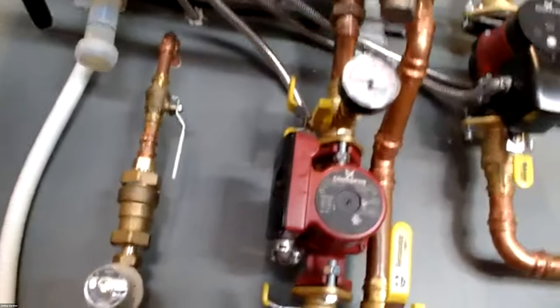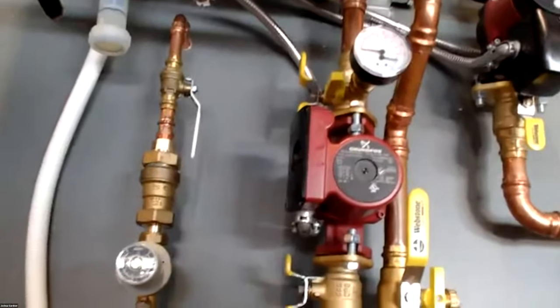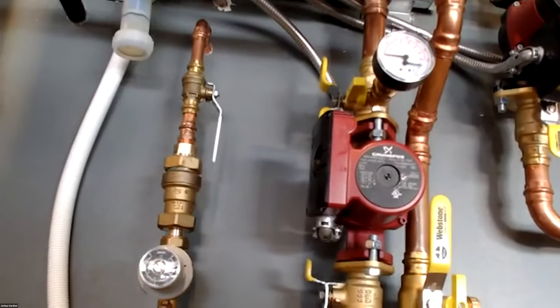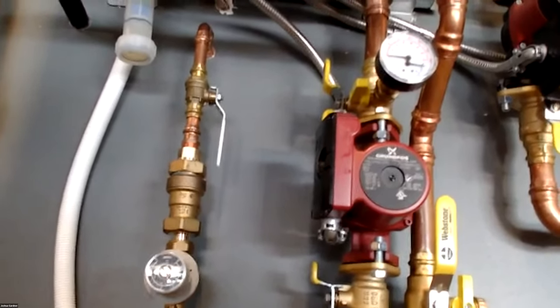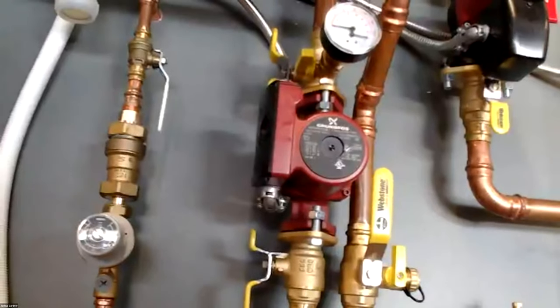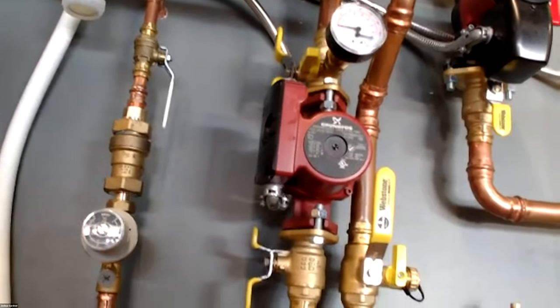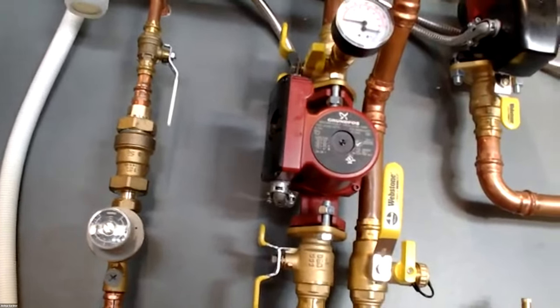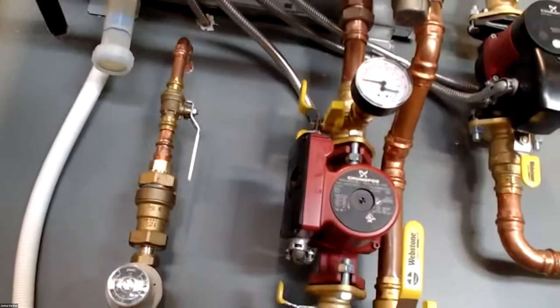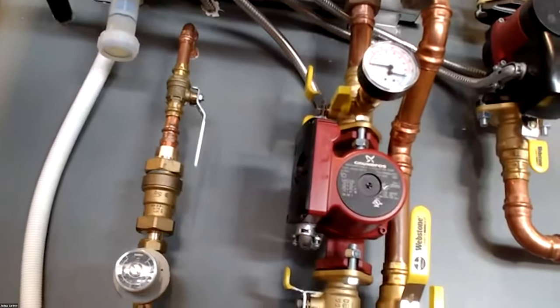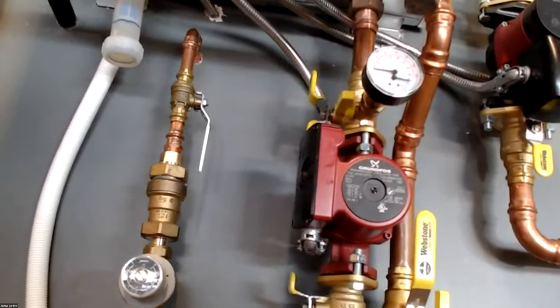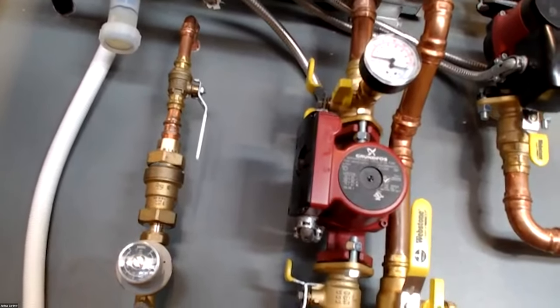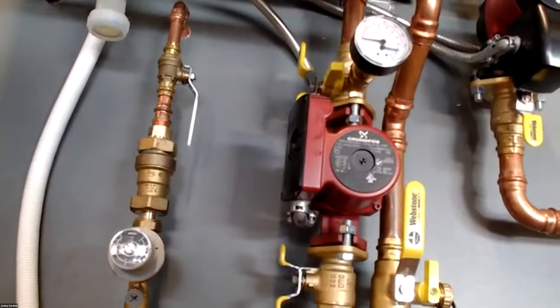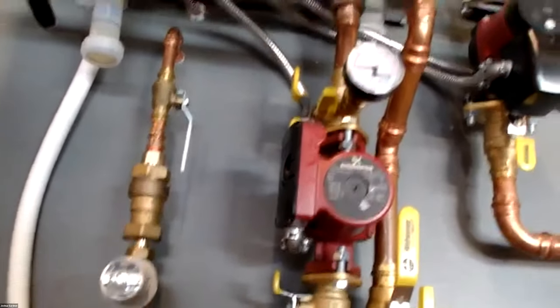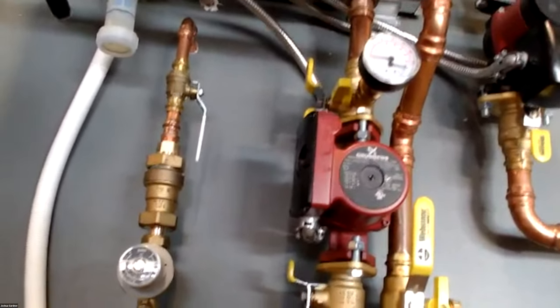But if you're doing a 155 and you want a full output, or a 199, with the Taco, you're going to want to use a 0013 or a 2400 series. 0013 is probably normally softer and cheaper. And for the Grundfos, you're going to want to use a 26-99. And that's if you want to get the full output of that 155 and that 199. All right, those are our pump recommendations. The application guide that's online on our website, and I'll pull it up and show you, has that chart in there, so you don't really need to remember that.